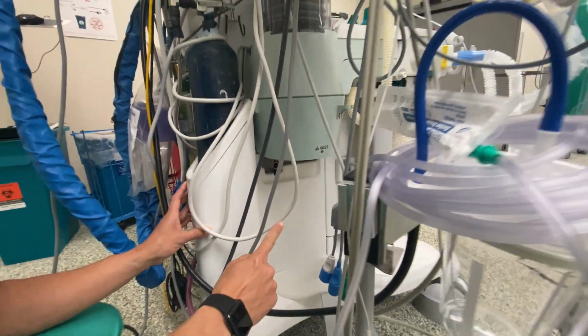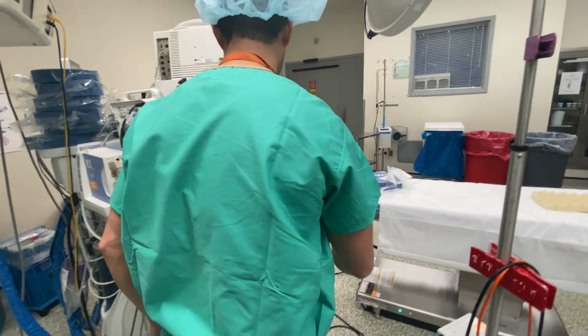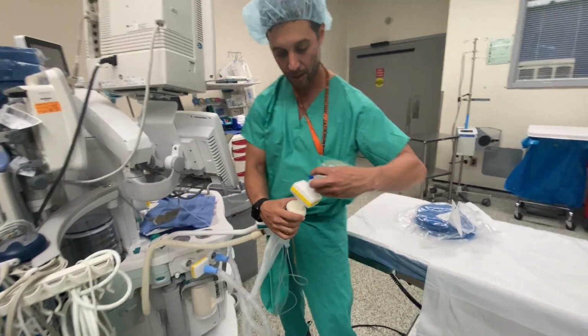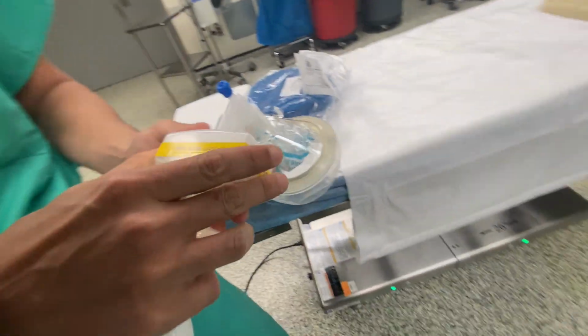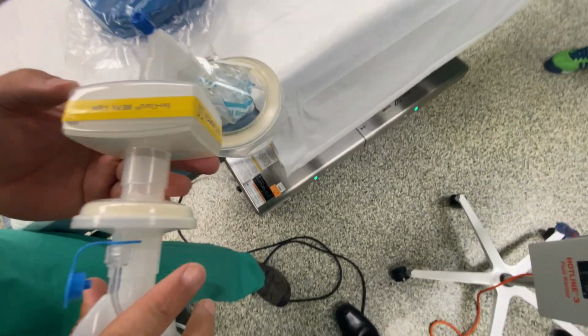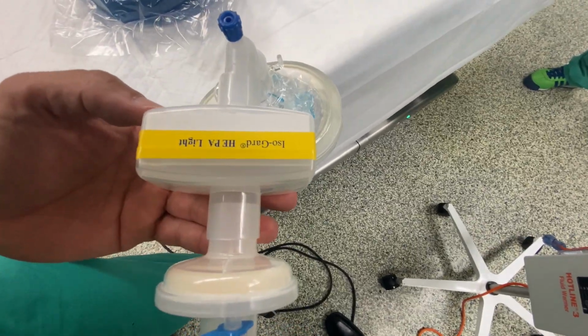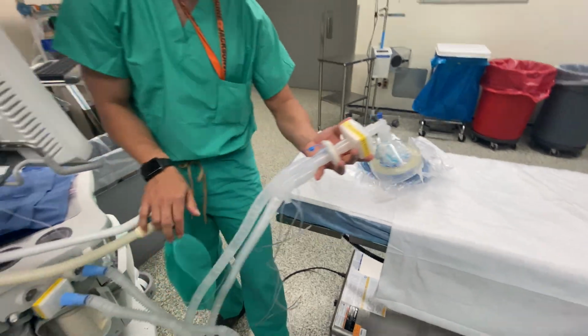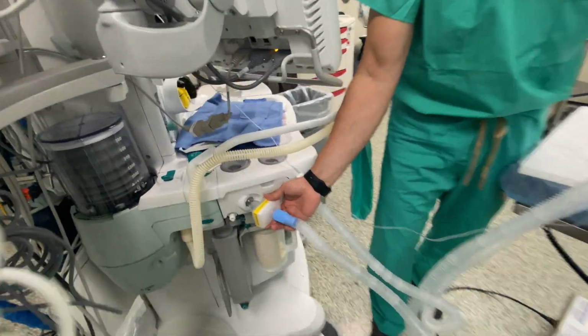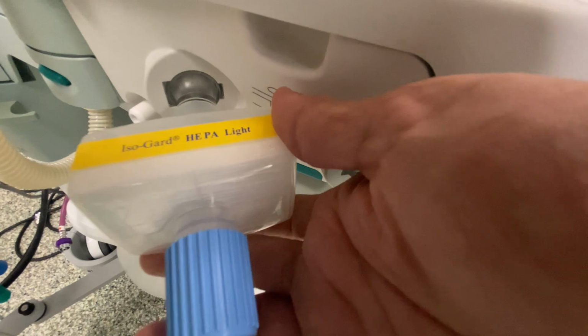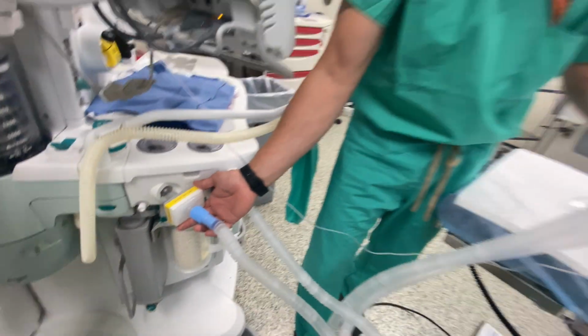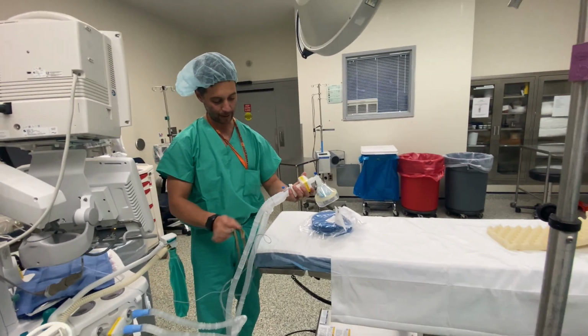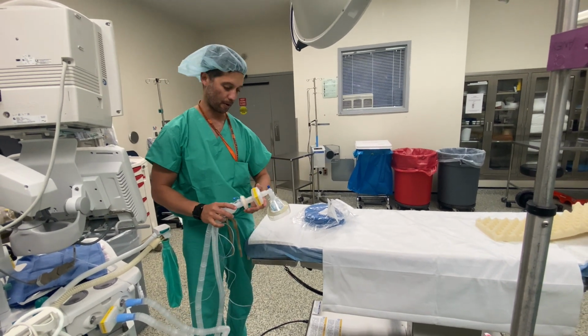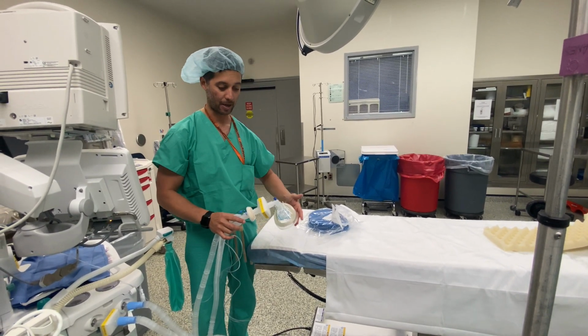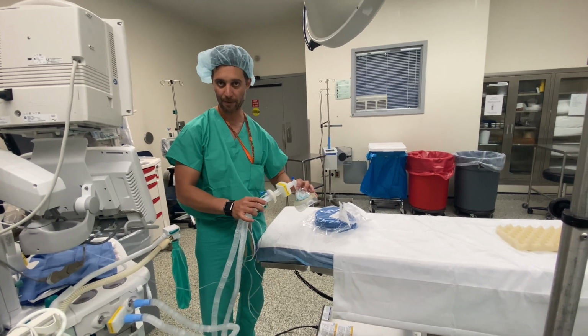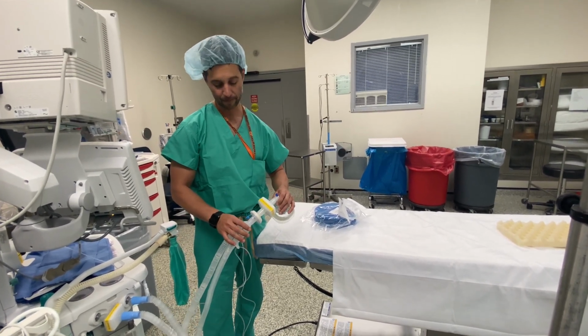So what respiratory does is they place filters at both of these two connection points on the anesthesia circuit. This is a viral filter, so it's down to 0.3 microns. It's written on the packaging if you have any questions. And then the other important part is we protect the machine in case the primary filter becomes overwhelmed with secretions. Because we're going to be ventilating patients, this is the scenario where you're doing this just while you're waiting for an ICU ventilator to arrive or become available. You can use this type of setup in the meantime, and that'll buy you some time.